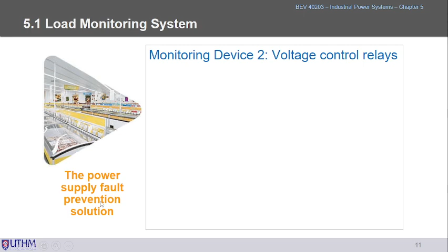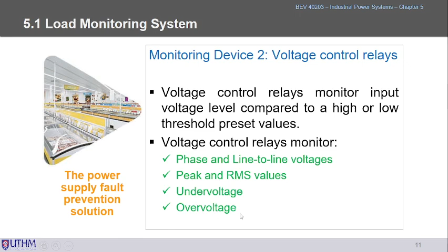At the load supply, we need to control and monitor the currents. For the incoming power supply, the voltage control is very important, and we try to maintain the voltage level at the preset level. That is why we need to know the high and low thresholds for those preset values. This voltage control relay will monitor, of course, phase voltage and line-to-line voltage, the peak and RMS value of the voltage, and under voltage and over voltage issues available in the IPS. So next is the load fault. As I told you just now, at the load level.